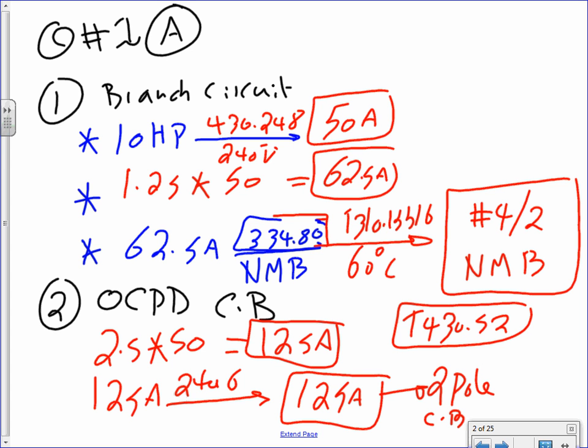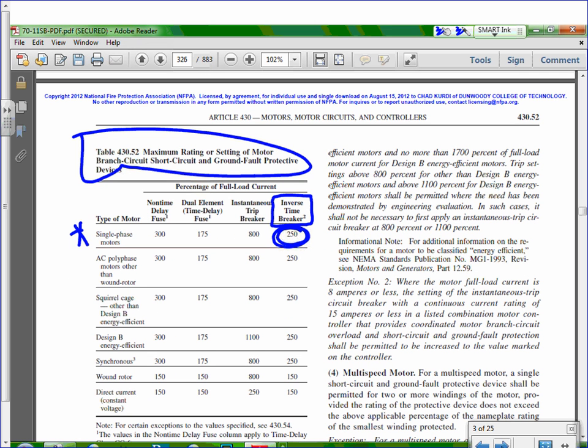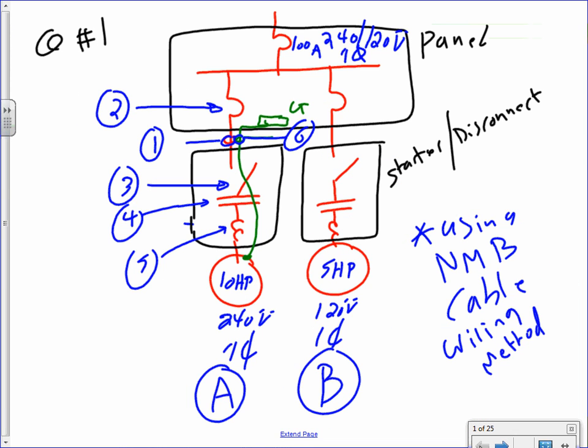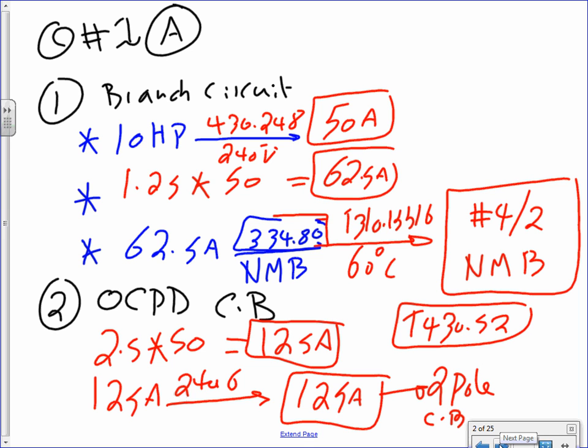We did this yesterday too. We said for circuit breakers, you're going to go to the 250. Remember that 250? You go to 250 to find it. Now, that 100 amp circuit breaker will not cut it then. I'm just going to change my size. It's a bit smaller here. So let's just say a 300 amp panel. Any comments? We size the overcurrent protection device and the branch circuits.